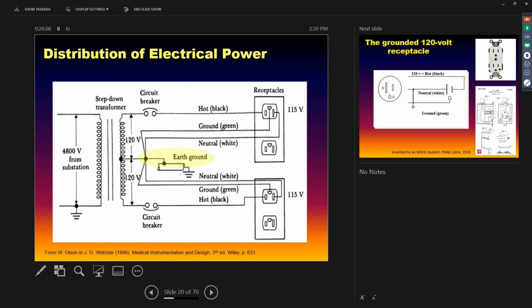Ground and neutral are bonded together, physically, electrically, mechanically bonded together, and that connection is also connected to the physical dirt. Somewhere outside, you probably can't see it anymore in your own homes, but there's a conductor coming out of your circuit breaker panel going into two typically 8-foot rods or so, separated apart, buried into the physical dirt.